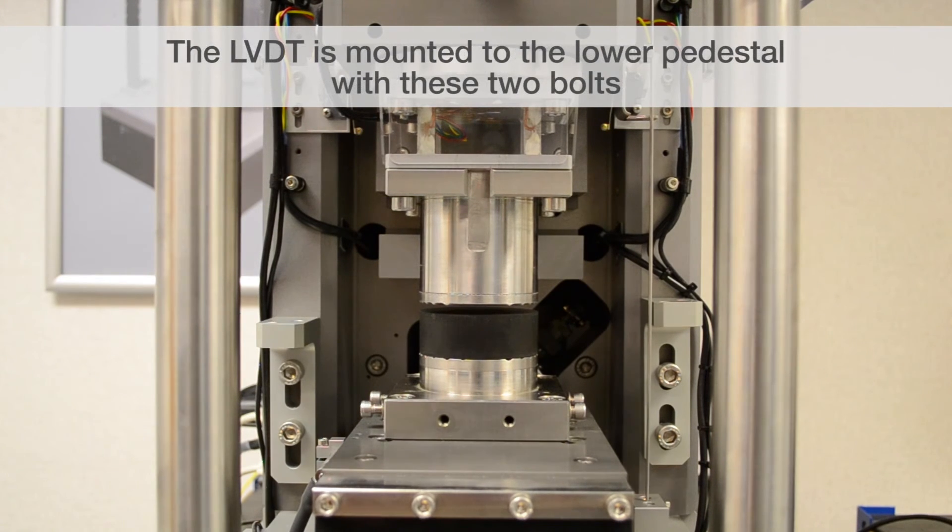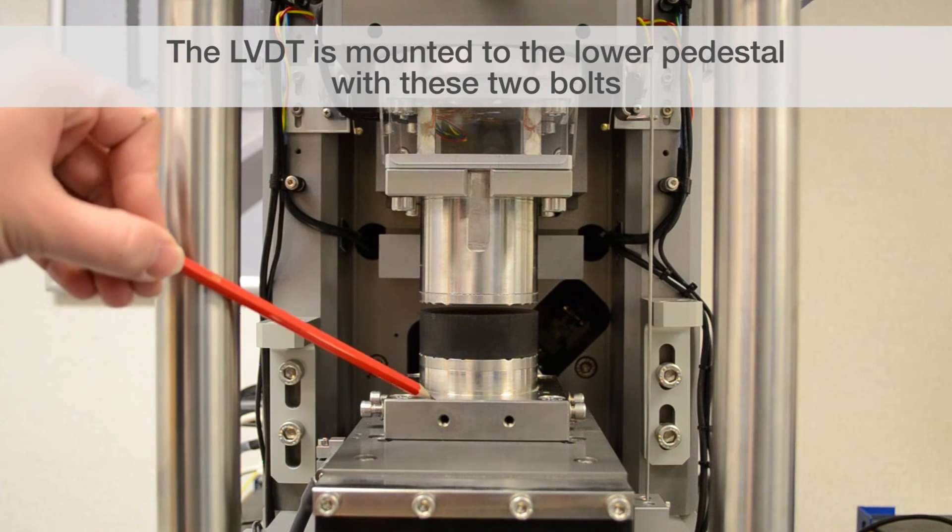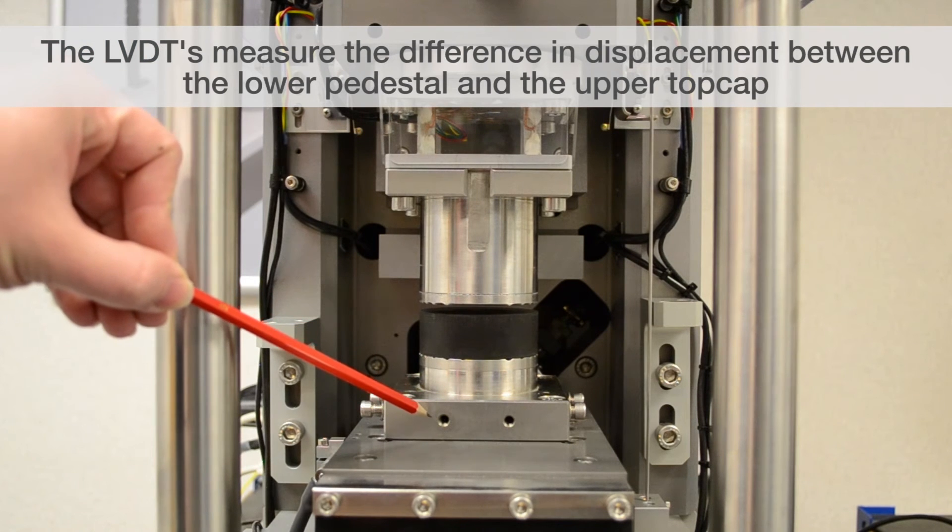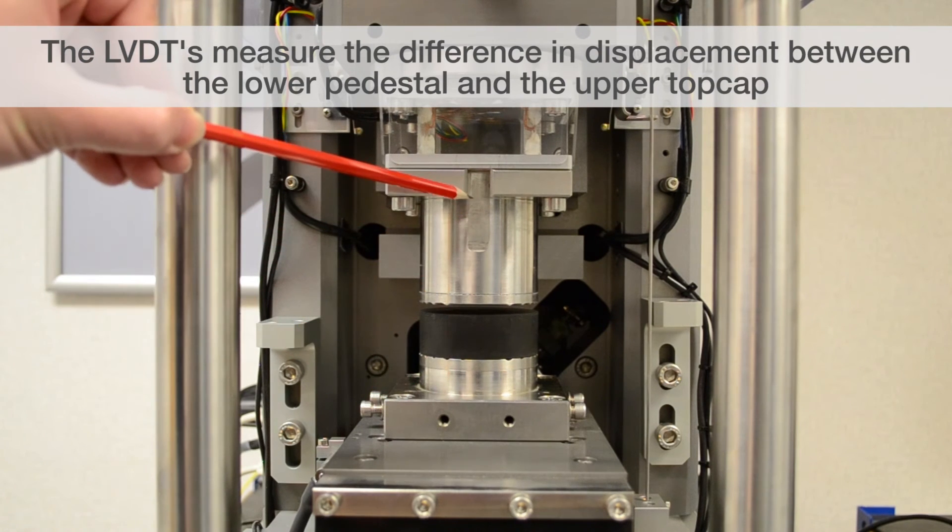The LVDT is mounted to the lower pedestal using these two bolts here and measures directly the difference in displacement between the lower pedestal and the upper top cap.